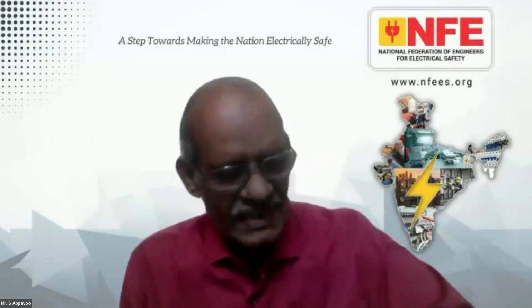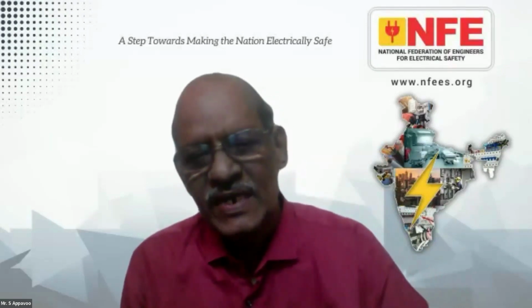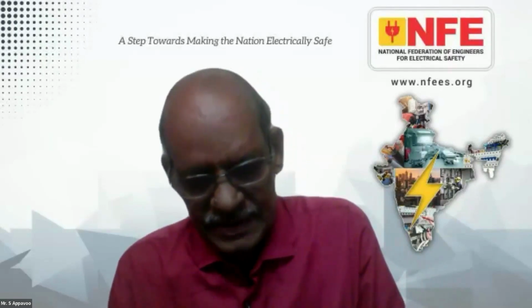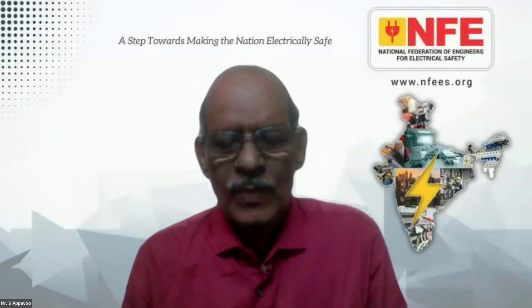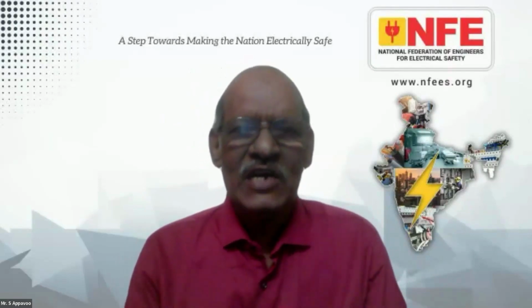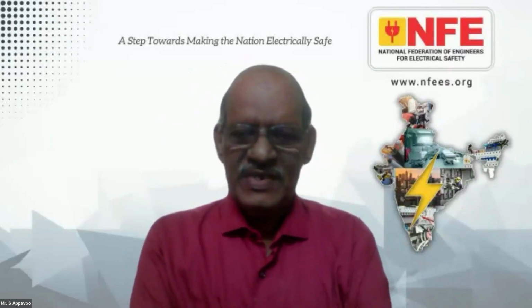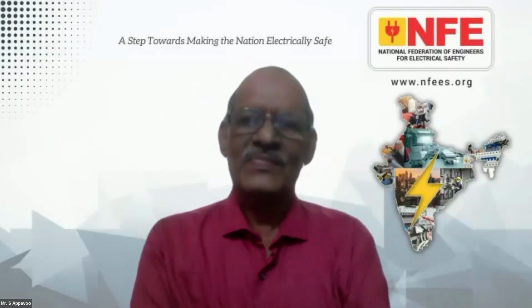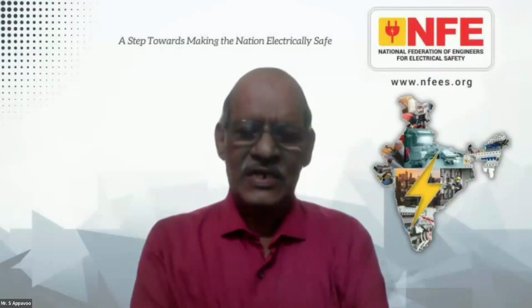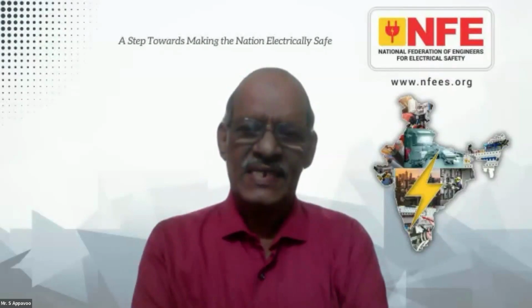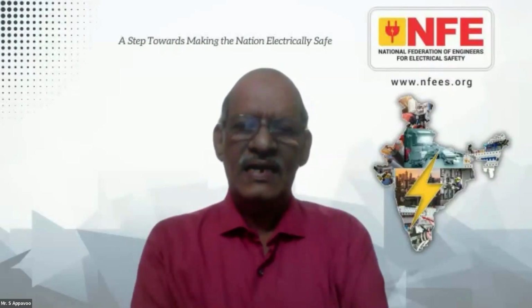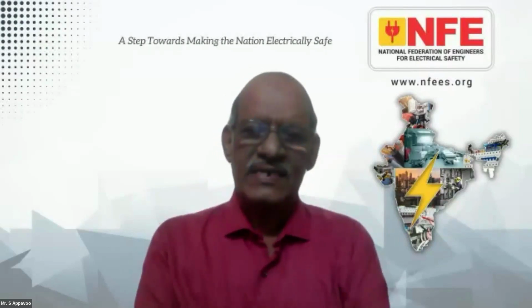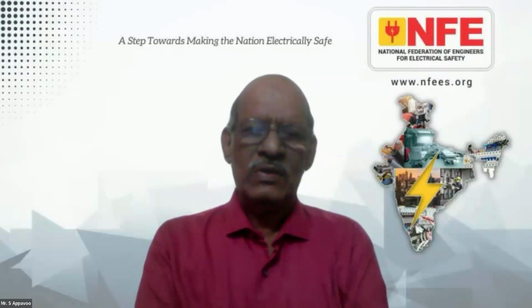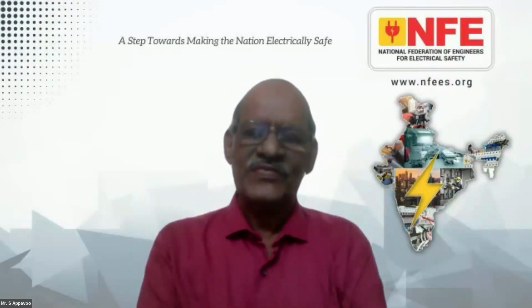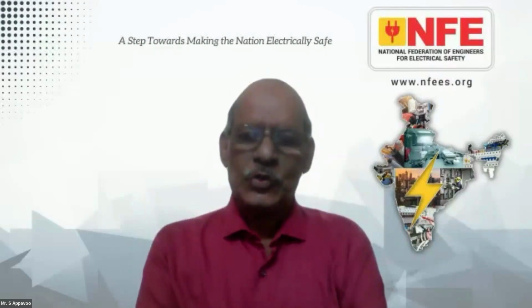For your question, it involves the complete design aspect of high voltage substations. Generally, for the global earthing system, we have to see the concept: proximity, interconnection, equipotentiality. This is the definition available for a global earthing system. We already have a dual standard, IS/IEC 61936 Part 1, to deal with this, and a derivative of this IEC standard is EN 50522. So as per regulation 14 and its definition, you can very well adopt these two measures.